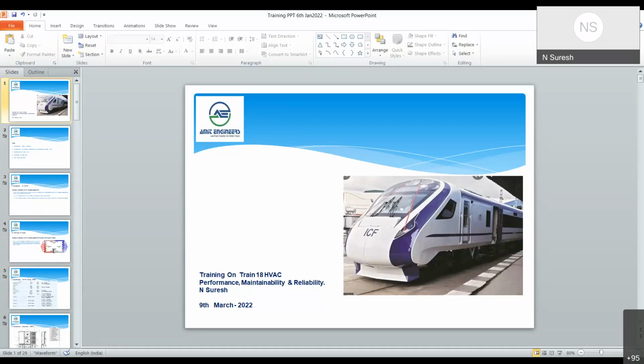To give a brief idea, this is the air conditioning system schematic. This is the compressor. What we are using is a hermetically sealed scroll compressor. It compresses the low pressure refrigerant to high pressure refrigerant. That is the work of the compressor. Inside the compressor there are mechanical parts, a fixed scroll and an orbital scroll, connected to the motor, which rotates and sucks the refrigerant and compresses it.